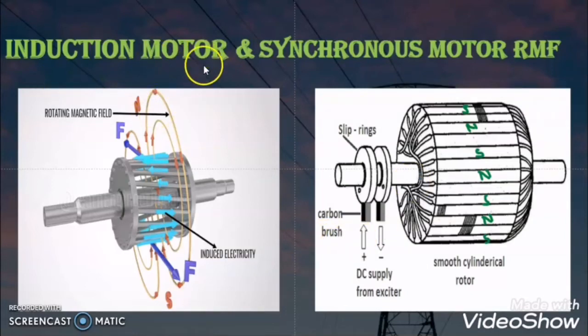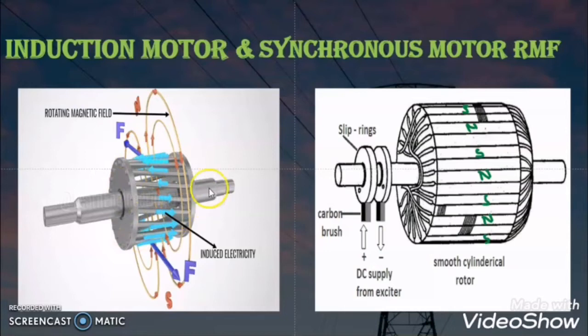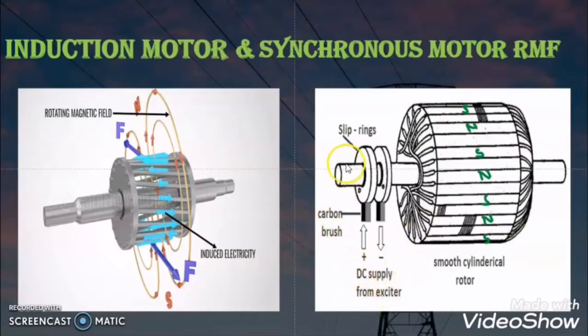In case of induction motor, we are not giving any power supply to the rotor. The induced EMF and induced current in the rotor bar is responsible for the power in the rotor. But in case of synchronous motor, we give DC power supply through the slip ring and carbon brush arrangement to the rotor windings.